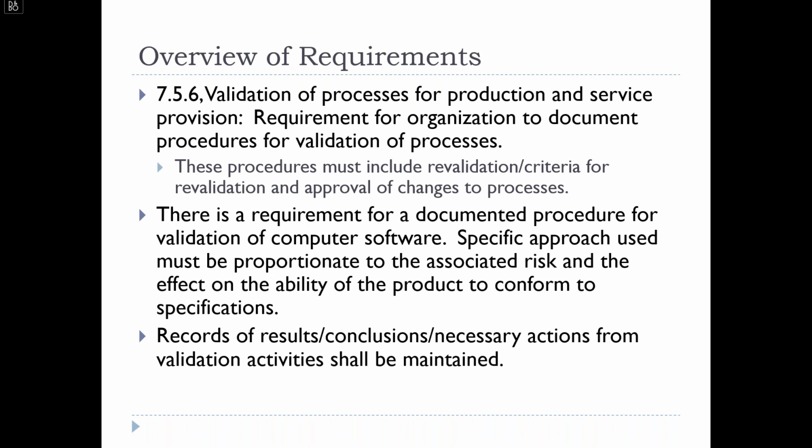We spoke about this earlier, but there is a requirement for a documented procedure for validation of computer software. The specific approach to be used must be proportionate to the associated risk and the effect on the ability of the product to conform to specifications. Records of results, conclusions, and any necessary improvement actions from validation activities need to be maintained.